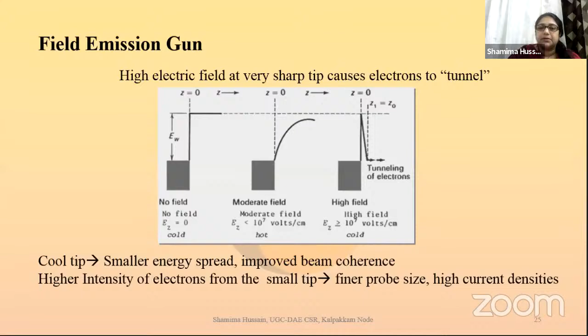This is what we're currently using. It could be a tungsten tip or it could be lanthanum hexaboride, whatever. But please see the difference here: there is no heater here. All we are doing is giving a very high voltage to this particular tip, and then using those anodes, etc., we accelerate the electrons down, right? So there is no thermionic emission here. This is called the FEG tip.